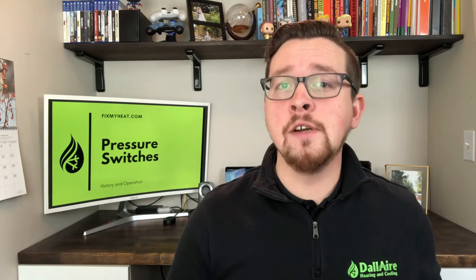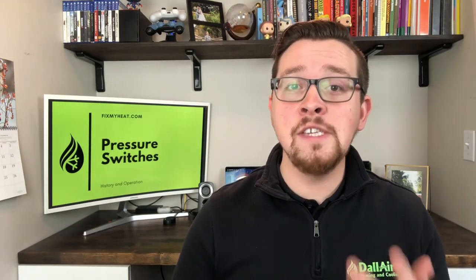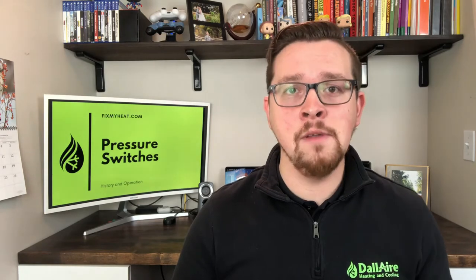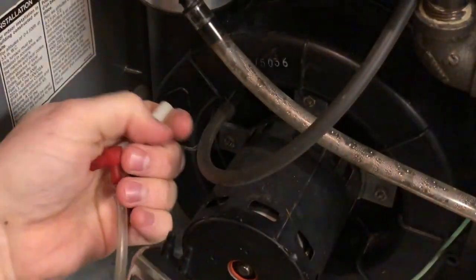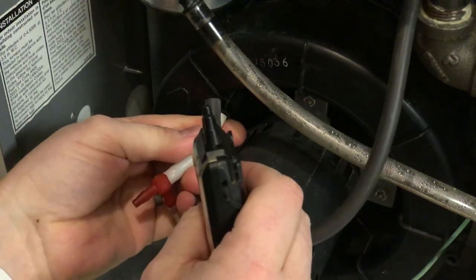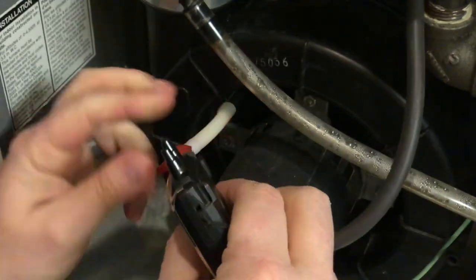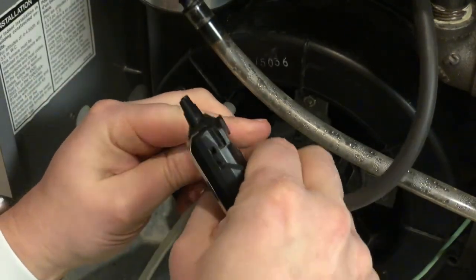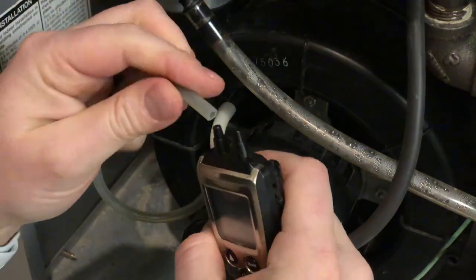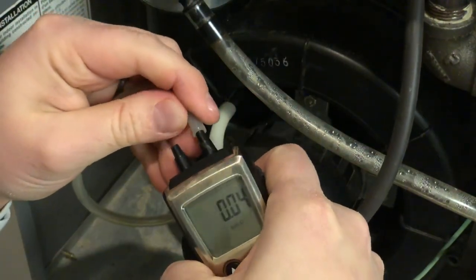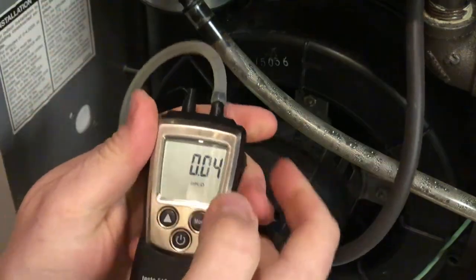There are some pressure switches that have two ports on them, and they connect to both the inlet and outlet side of the exhaust assembly. These are called differential pressure switches, and they measure the difference between the inlet and outlet pressure. If you were to take a manometer and connect it with a T into the pressure switch tubing, or even directly to the exhaust assembly pressure switch tubing port, you would read the pressure at which the air is being pushed or pulled through that tubing.